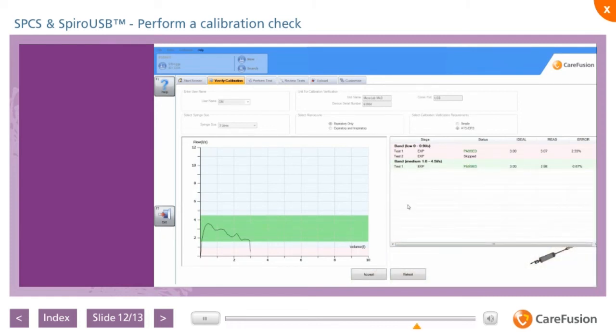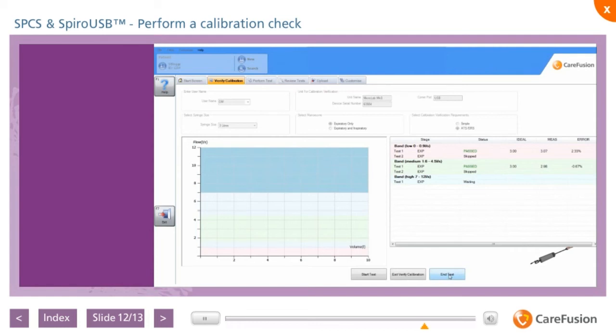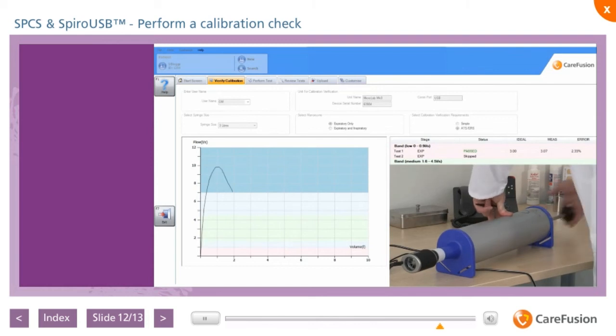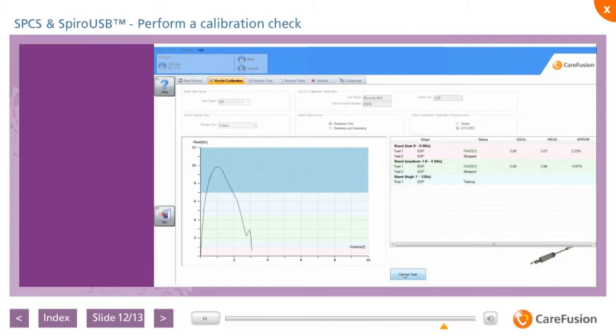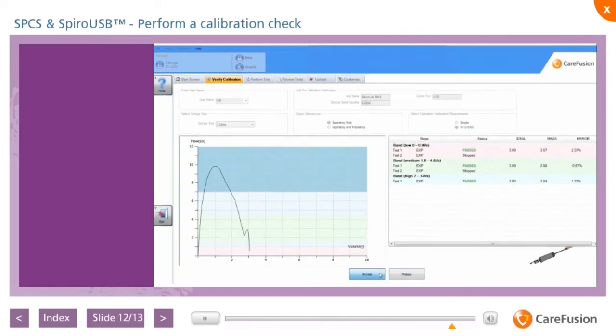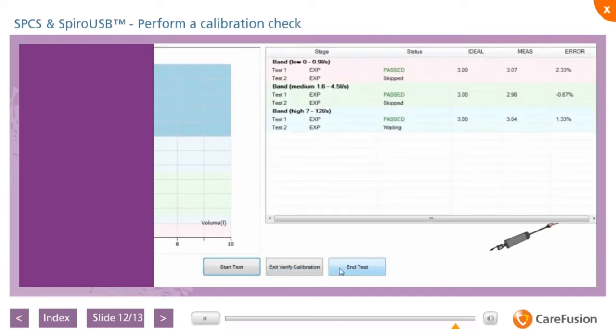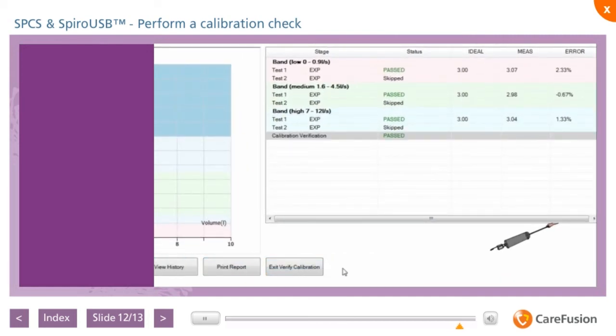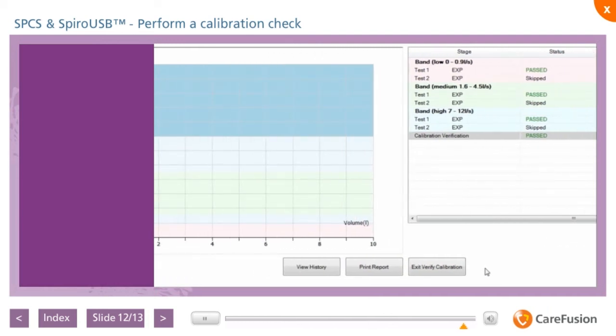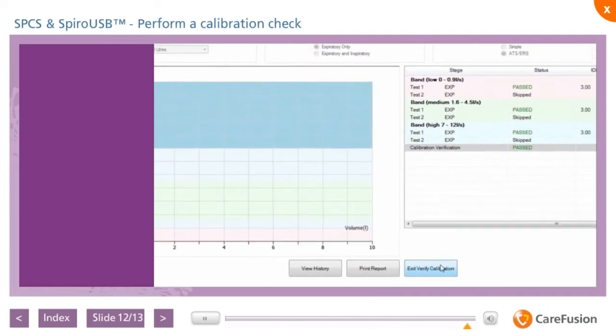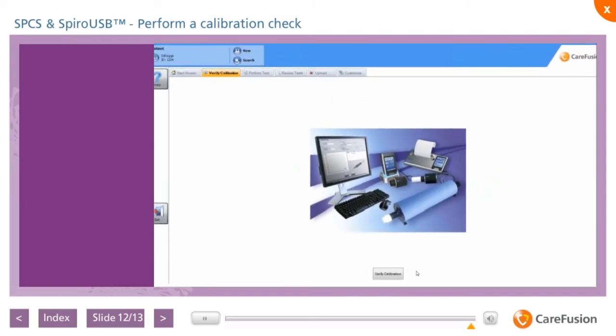The screen will show a pass or fail status for each maneuver performed. The spirometer should pass on each flow rate. The calibration history can be viewed for the spirometer by selecting View History. This will show the name of the person who performed the calibration verification, the date, time, and the calibration status for each test. If 3 maneuvers have been performed, simply select Exit the calibration screen. By selecting Print Report, a printed report of the current calibration will be available for printing and storage.